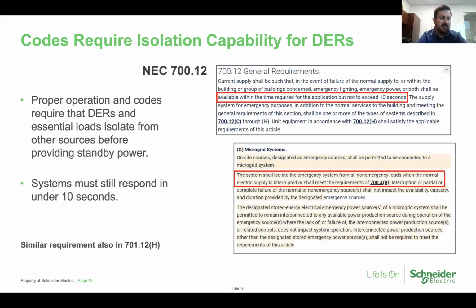Well, that's great, but if we're using, let's say, a battery energy storage system in parallel with utility, I still want to be able to use it for resiliency, for standby power, for emergency operations if there is an outage of some kind. Well, there's some rules around how to accomplish this. First thing we got to understand, and we'll cover this during the sequence of operations side, is you have to make sure that you can isolate that equipment from the utility power source so it can come up in a grid forming mode rather than a grid synchronized mode without backfeeding the utility or overloading. That's just inherent to the operation of the equipment.